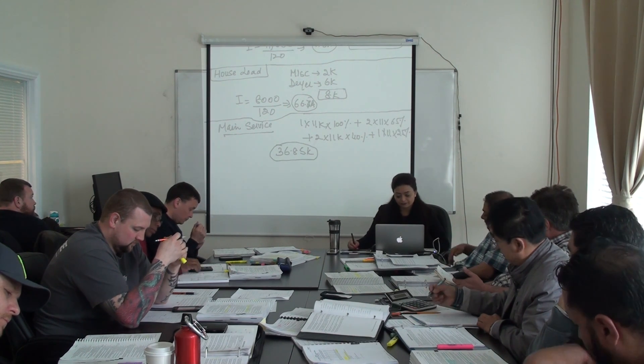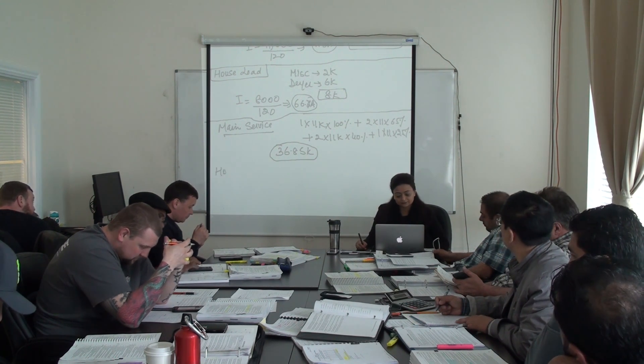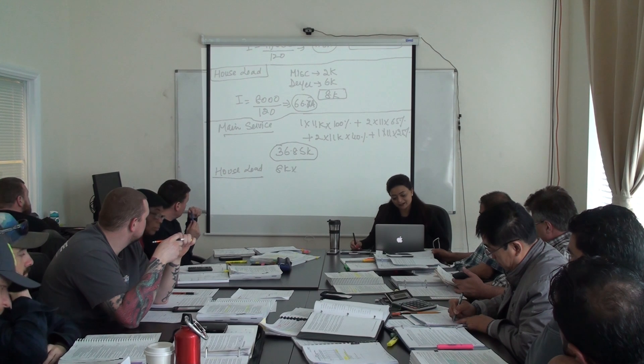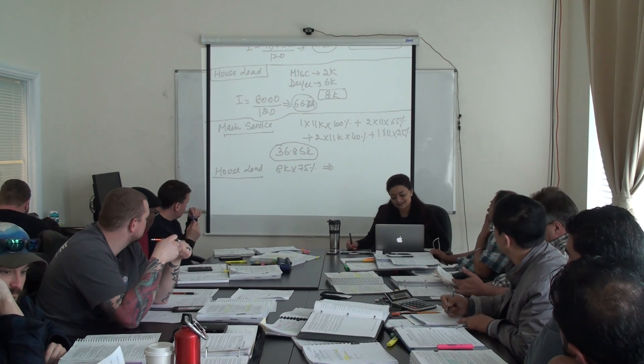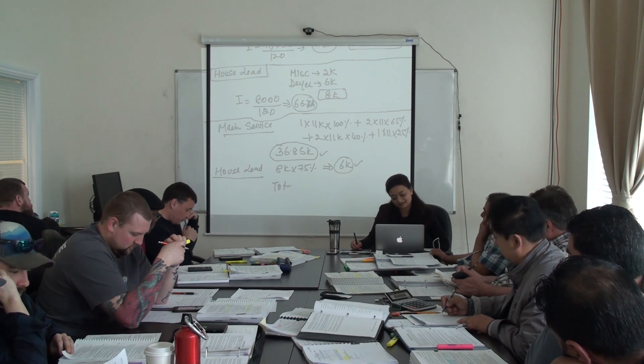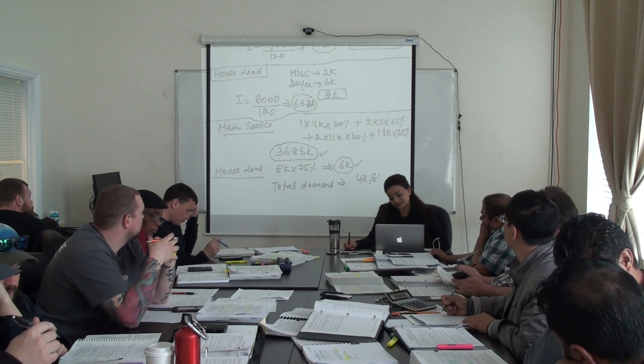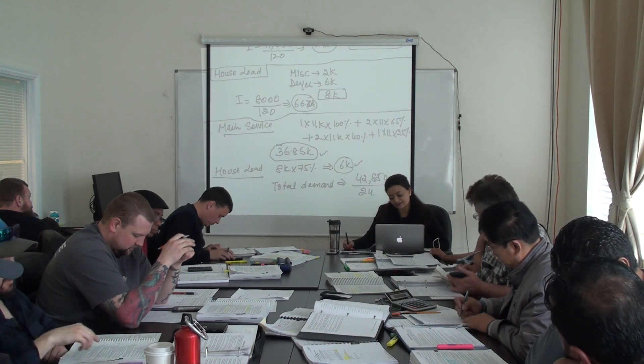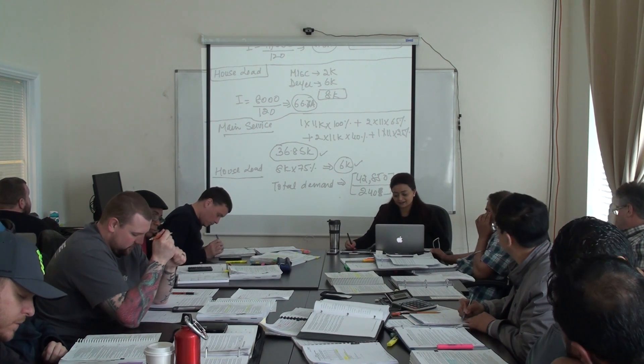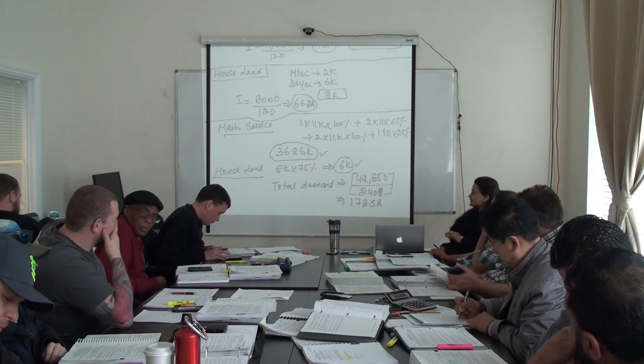So this is the whole thing about suites. Now house load — because there was no heat there either, life was easy. We take 8K and multiply by 75%, which is 6K. Add item 1 and item 2 and your job is done. Total demand? 42,850. Voltage is 240, single phase — so no square root of 3. When you do the math: 178.5 amps. I should get off the screen so you guys can see exactly what I just did.